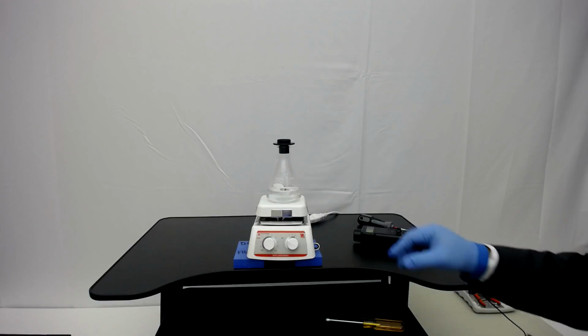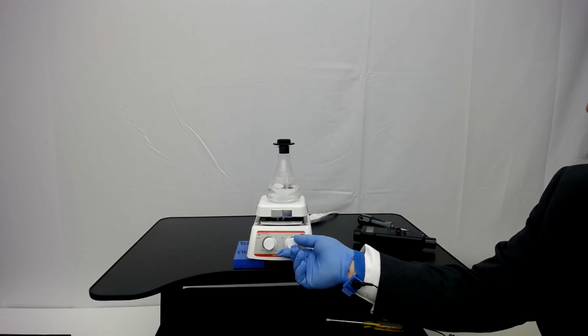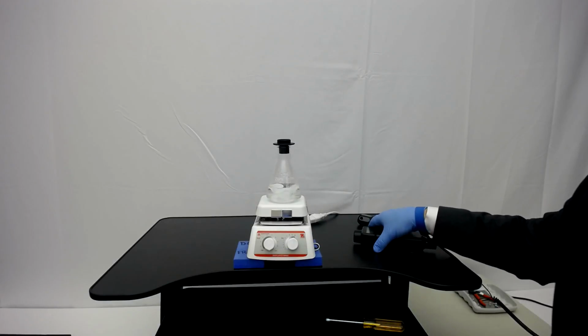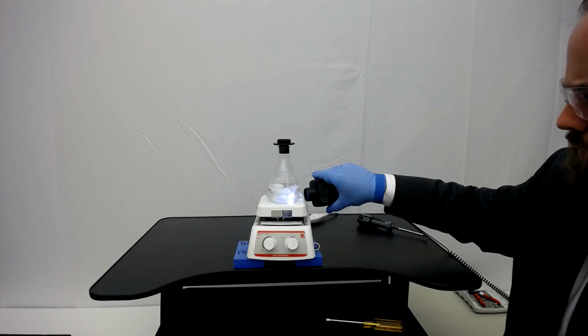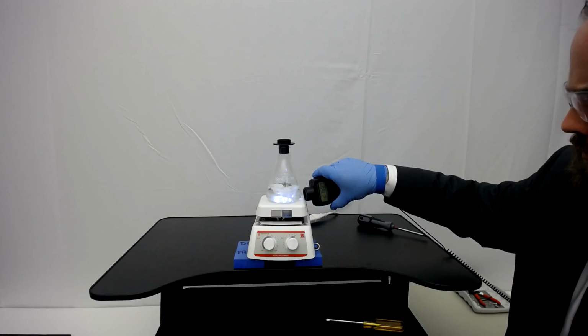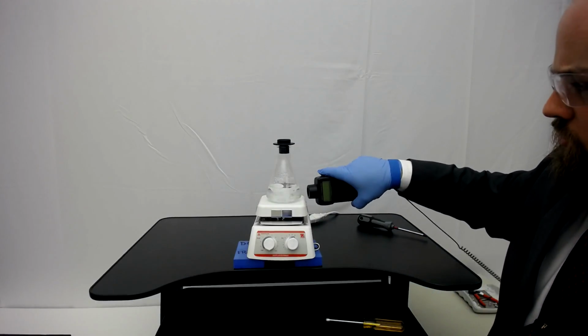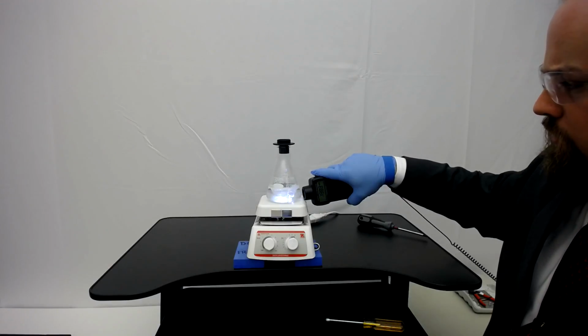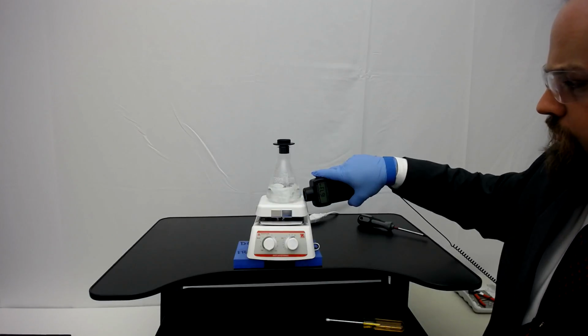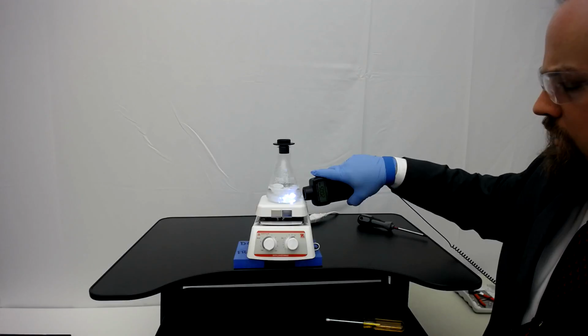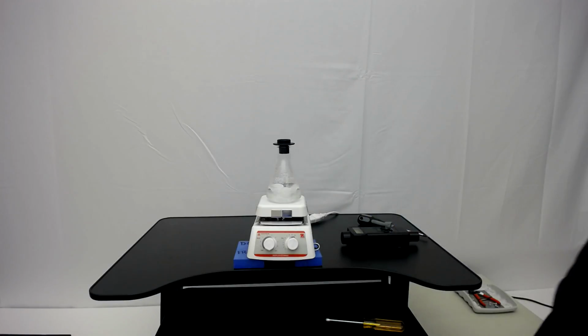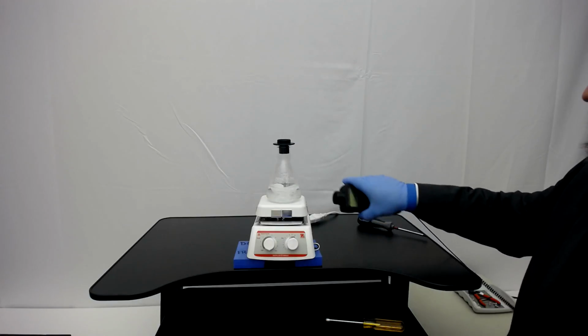We're looking good there. Then we're going to increase the speed to 10 and take a reading on this. Again, the tachometer gets 2 pulses, so whatever you read on the tachometer, you're going to cut it in half. It's fluctuating a little bit, which you would expect, but it's right around 1,000 RPM. You want it to be under 1,500 RPM. So that's a good calibration here.